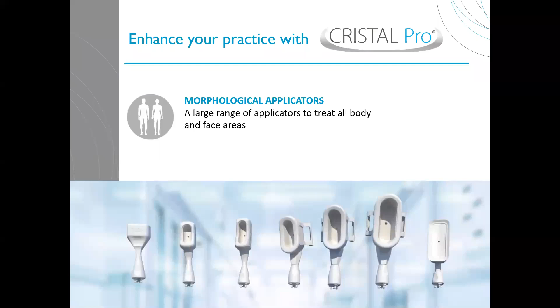So as you know, cryolipolysis is the combination of cold and suction. Regarding the suction, Dileo engineers developed a smart aspiration adjustment. It allows a precise selection of the suction wanted for a better patient comfort, from 0 millibars to -700 millibars. The majority of our competitors today are only using levels of suction, where you don't really know how much the vacuum level is, which is not very precise and doesn't adapt to the patient's feelings. Leah will show you which kind of suction you need depending on the protocols later in this presentation.